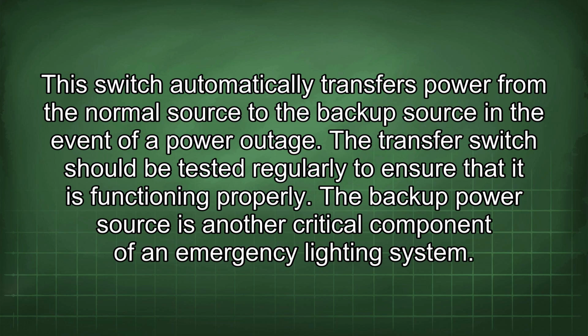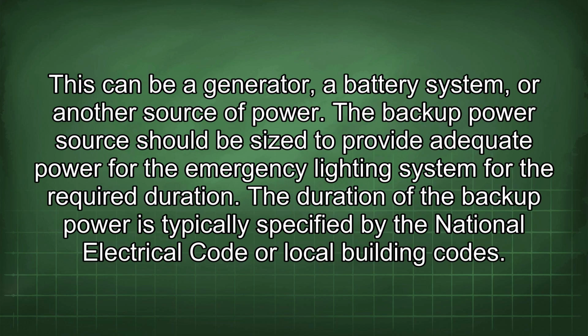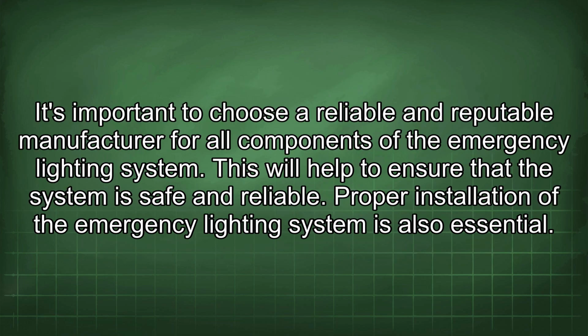The backup power source is another critical component of an emergency lighting system. This can be a generator, a battery system, or another source of power. The backup power source should be sized to provide adequate power for the emergency lighting system for the required duration. The duration of the backup power is typically specified by the National Electrical Code or local building codes. It's important to choose a reliable and reputable manufacturer for all components of the emergency lighting system. This will help to ensure that the system is safe and reliable.